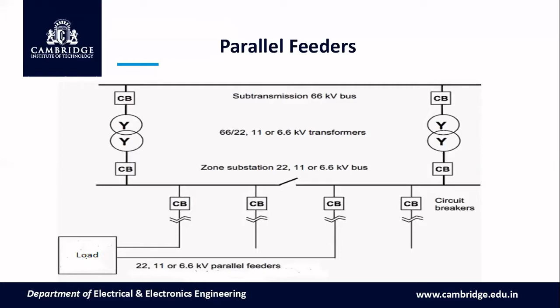Next is the ring main or loop. Two or more radial feeders connected from the same or different secondary substations are called loop feeders. Loop feeders are normally arranged in two ways: either an open loop system or a ring loop system. The primaries of the distribution transformers form a loop starting from the substation, going around the area where loads have to be supplied and coming back to the substation.